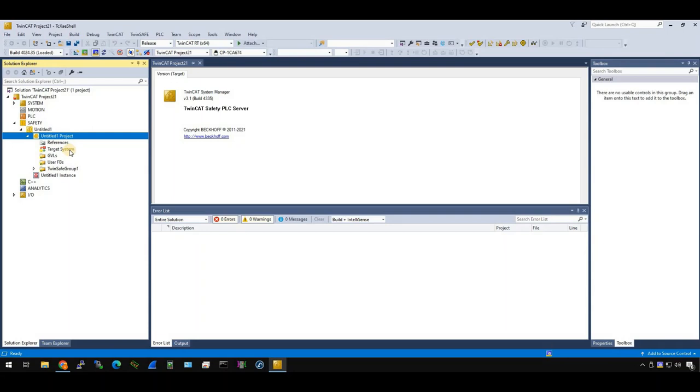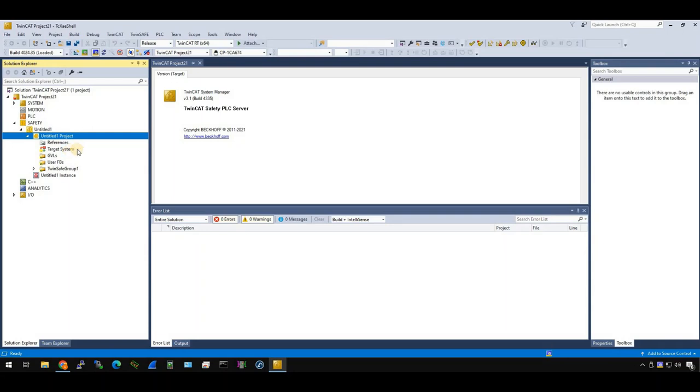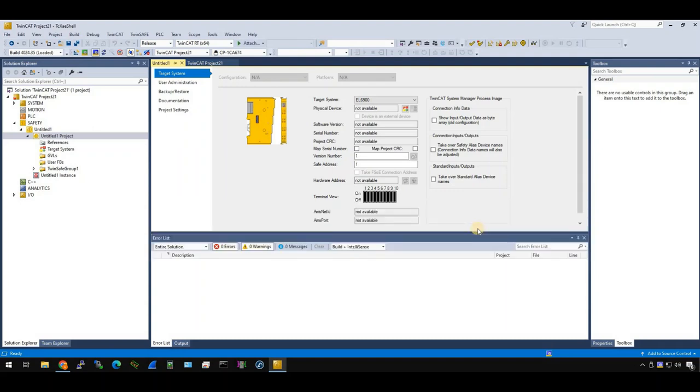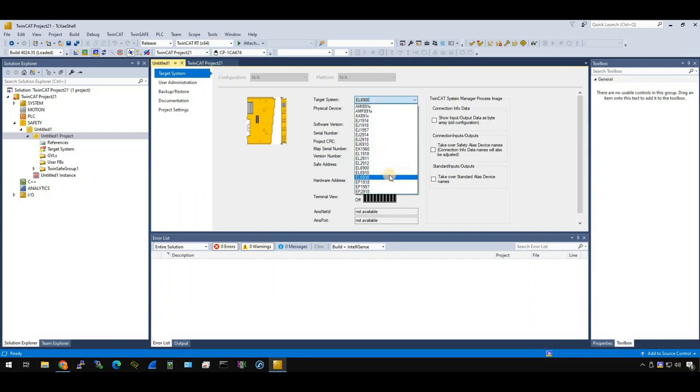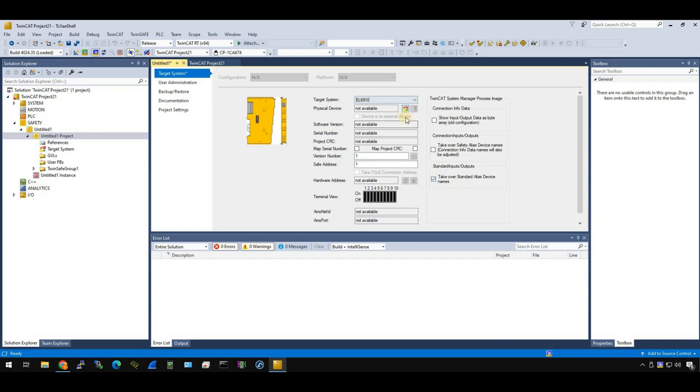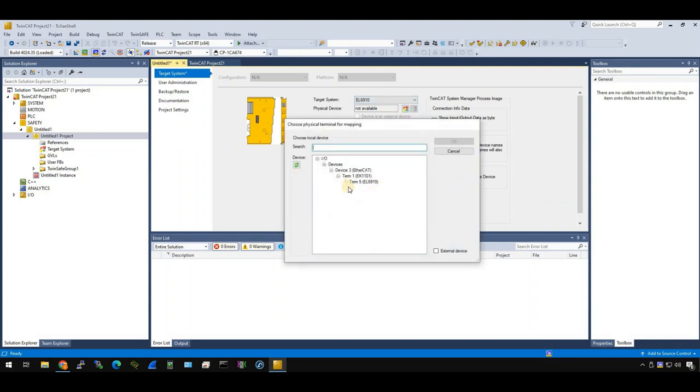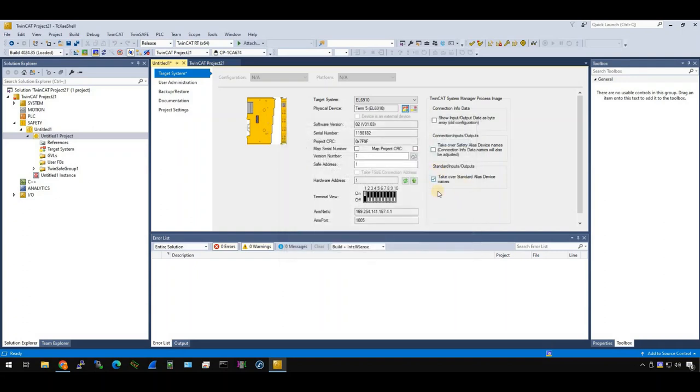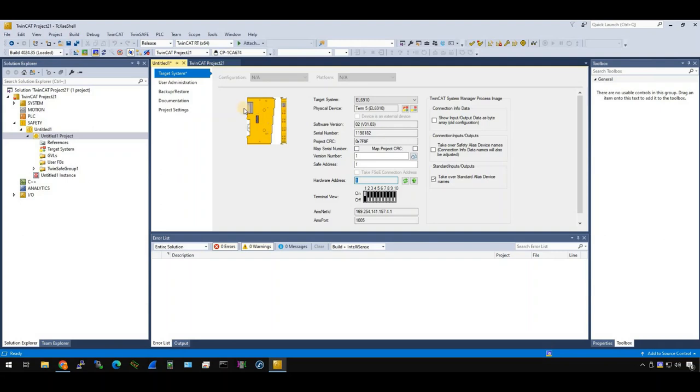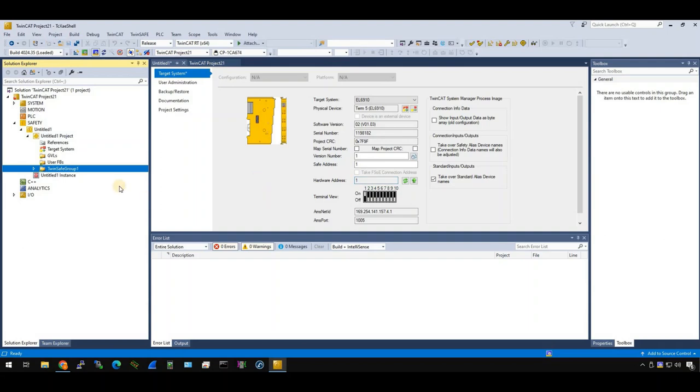Safety project is inserted in your TwinCAT system. Okay, we'll browse it. The first one need to configure the target system. Click it. So what's the target system? The target system is actually the safety logic terminal. In the default, EL6900 is used in here. We need to change it to EL6910. And press the add button. And here, you'll find the terminal file. The terminal file is the EtherCAT network that we scanned before. The terminal file is the safety terminal logic. Press okay. Then some information that you need to take care: the safety version, serial number, CRC, and also the hardware address. So the hardware address is a dip switch when you take out your safety logic terminal. There is a small device in this side. Then you need to turn this on/off to configure your safety address. In here, the safety address is configured at 1.